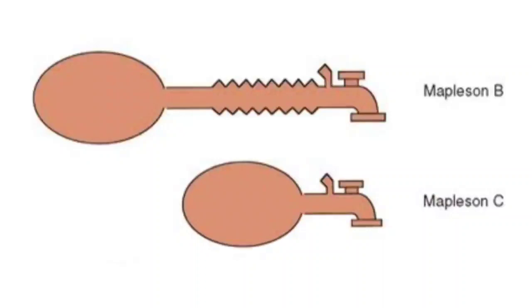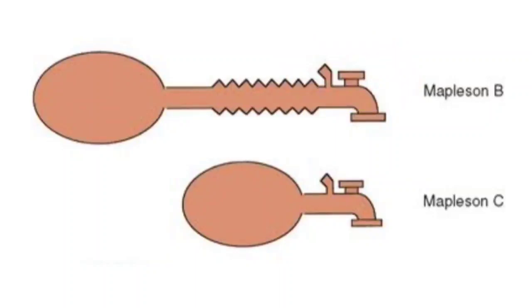These are Mapleson B and C circuits. As usual, these circuits also have four parts, but the difference from other circuits is the position of the APL valve and fresh gas flow inlet, which are at the patient end, while the reservoir bag is at the machine end. Another difference is that the corrugated tubes are shorter in these circuits, with the C circuit having a particularly short tube, as you can see in the picture.